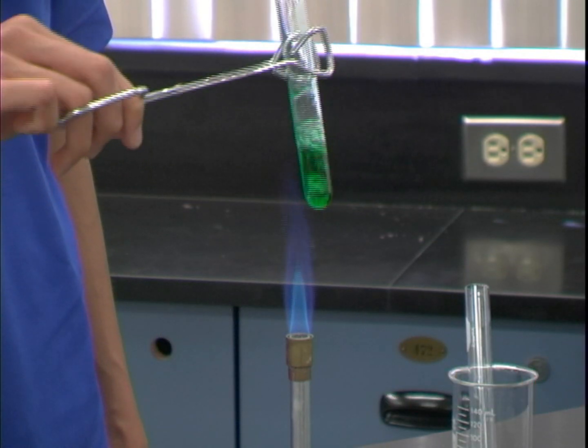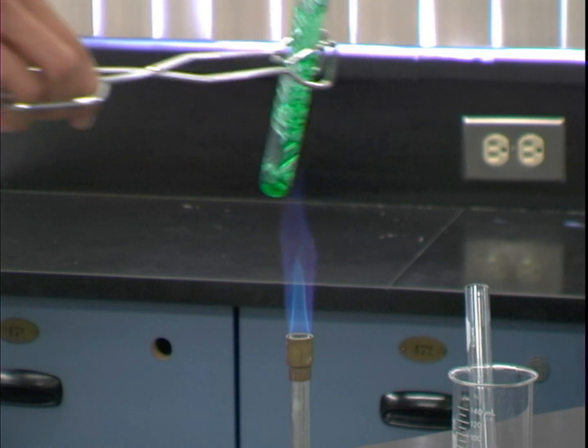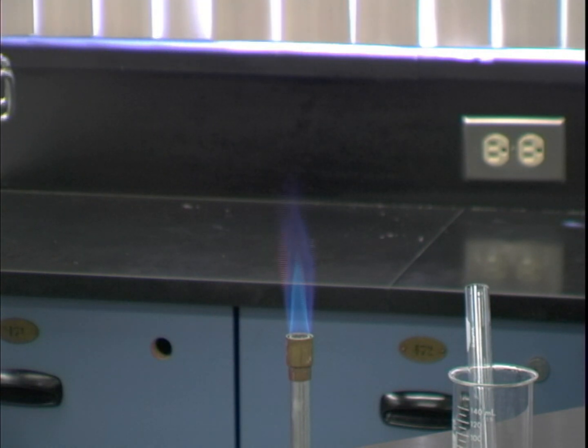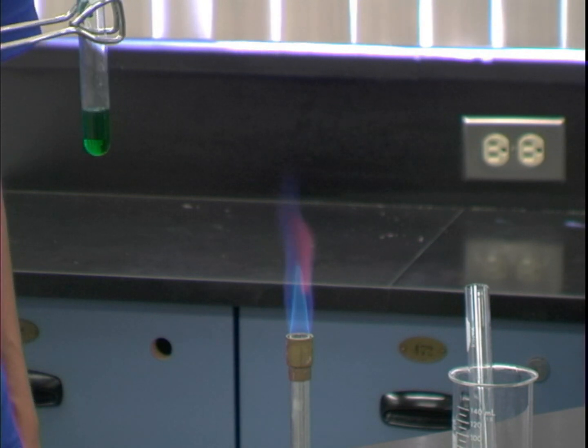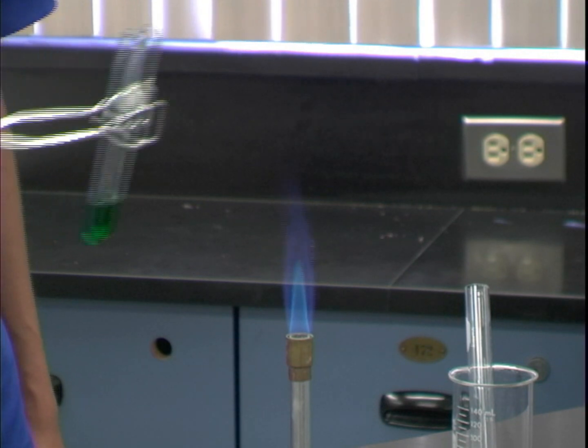Use protective clothing for hot equipment. Open flames also don't mix with skin or clothes, so never reach over an open flame. Don't mix flammable materials with fire. They are called flammable for a reason. They catch on fire. Don't throw away lit or burning things. They can catch the trash on fire.